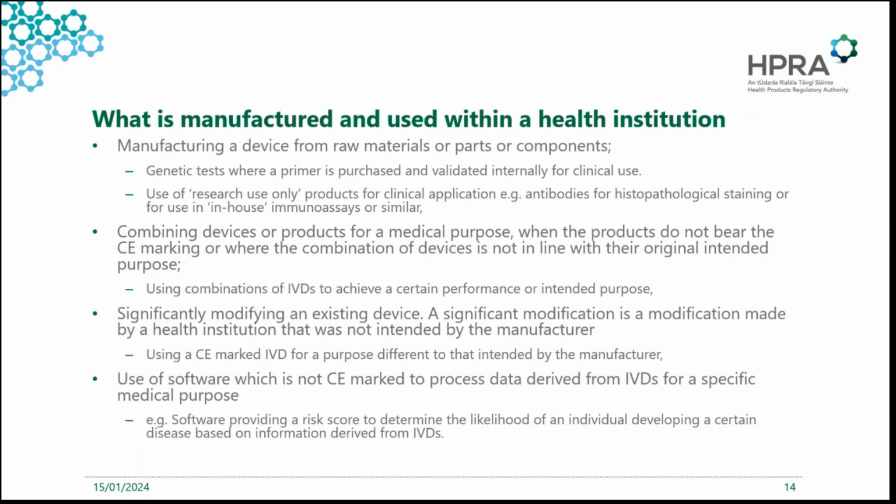So software to create adjusted calcium would typically not be an in-house IVD. But if you were doing something more complicated, such as providing a risk score based on the outputs of some IVDs and other information, for example, taking BRCA gene status and using one of the breast cancer models to take familial history and epidemiological models and collate all that information to provide a probability of somebody developing breast cancer over the course of 5, 10, 15, 20 years, then that's more likely to be in the in-house IVD space, and less likely to be the simple calculations such as percentages or adjusted calcium, for example.